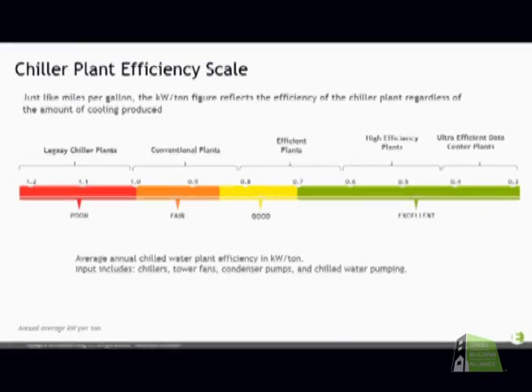On the right-hand side, it's really only data centers that you're going to see that extreme efficiency, and that's partly because you have a very definite load. You know what it's going to be. It's consistent throughout the year. So even in winter, in weather like this, when you get a little bit more efficiency, you are always going to have that constant load. In an office building, that's not going to be the case. You shouldn't have a ton of cooling in a space like this and this time of year.